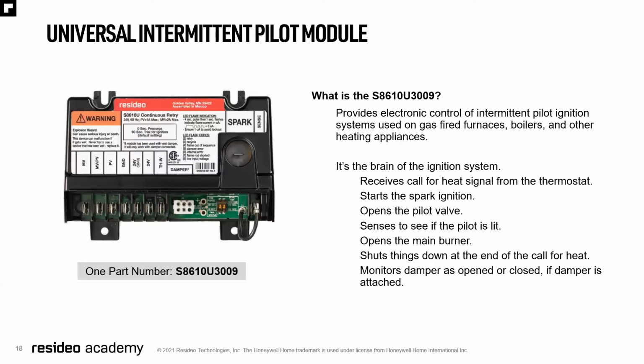Universal Intermittent Pilot Module. What is the S8610U3009? Provides electronic control of intermittent pilot ignition systems used in gas-fired furnaces, boilers, and other heat applications. And additionally, when purchased as the Y kit, is a recontrol that will take almost any standing pilot to an intermittent pilot by replacing the gas valve, the wiring harnesses, the igniter, pull out the thermocouple, put in the correct igniter, and a spark wire. It's quite simply the brains of an ignition system.